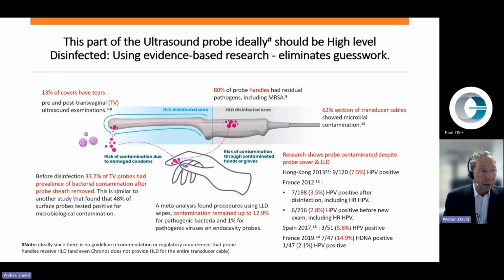This is similar to another study that found that 48% of surface probes tested positive for microbial contamination, that is, bacteria, fungi, or viruses. Let's turn now to the probe handle. 80% of probe handles had residual pathogens, including multi-drug resistant organisms such as MRSA. 62% of transducer cables showed microbial contamination, particularly in the area right near where it's handled. A meta-analysis found that in procedures using low-level disinfection wipes, contamination remained in approximately 13% for pathogenic bacteria and 1% for pathogenic viruses on endocavity probes. Research shows that probes are contaminated despite probe covers and low-level disinfection.